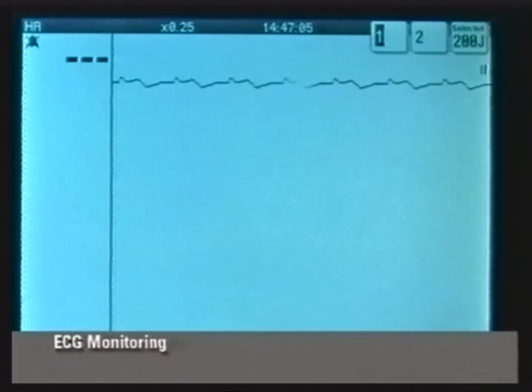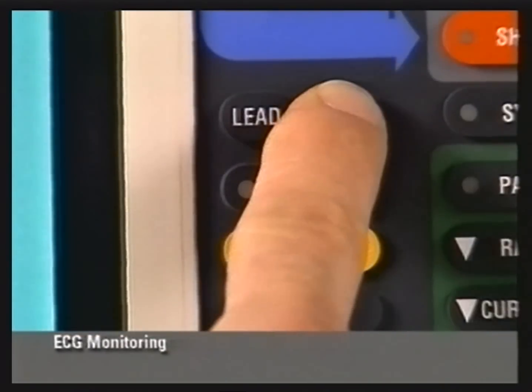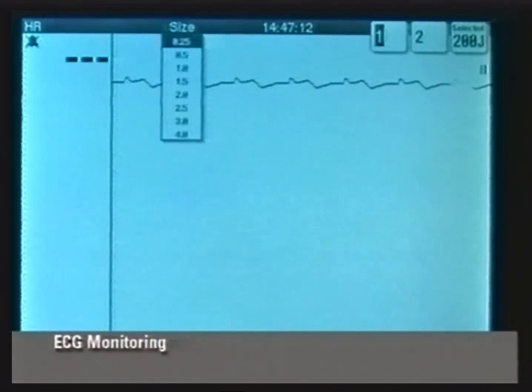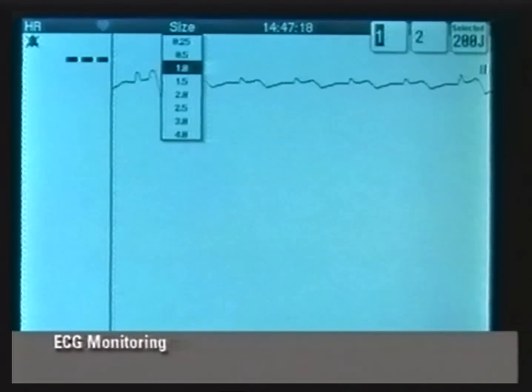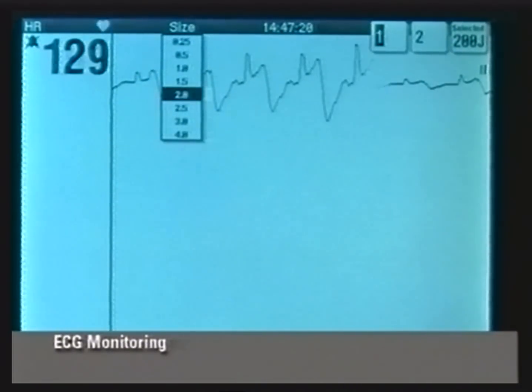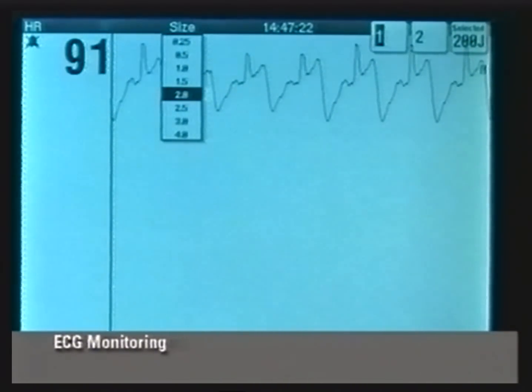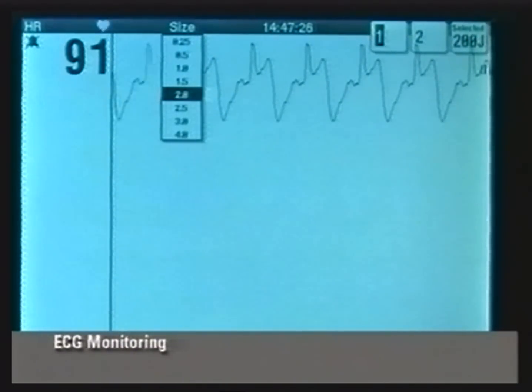If the heart rate counting is inaccurate, adjust the ECG size. Press the size button. The size menu appears. Continue to press the size button or rotate the selector to change the size. Note that the ECG trace in channel 1 automatically changes as each size is selected.